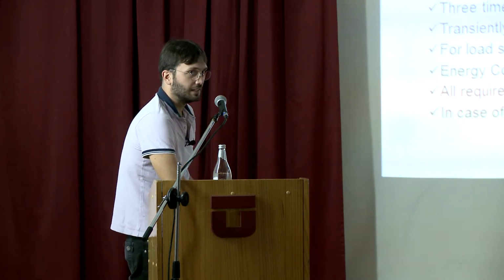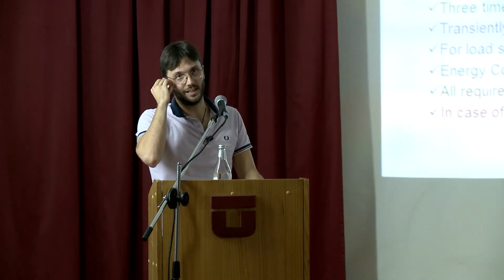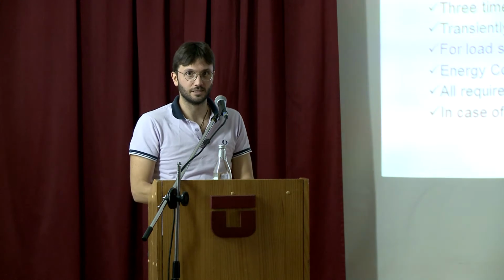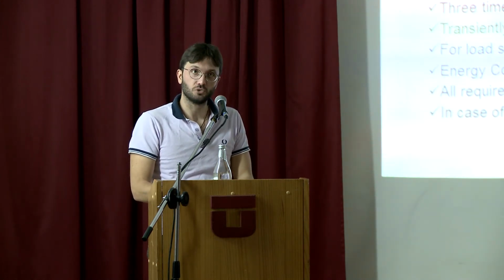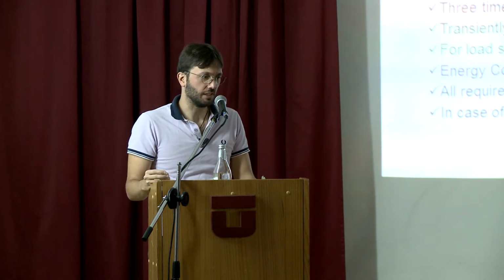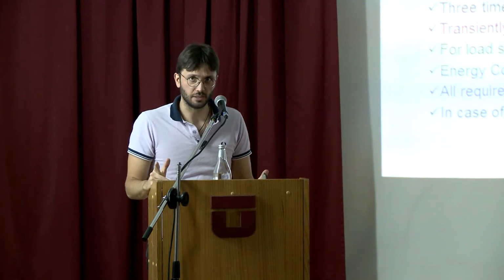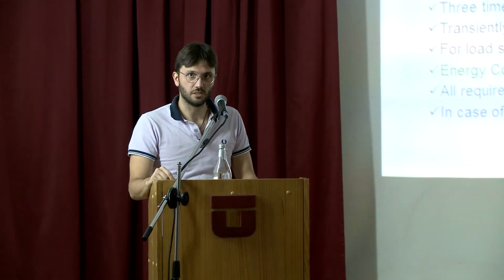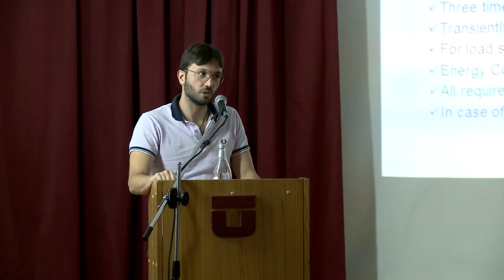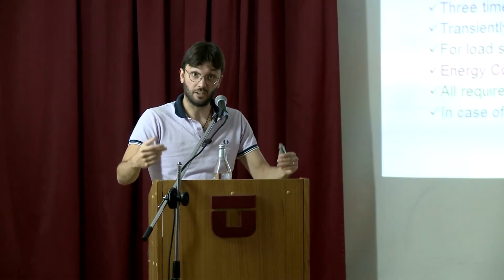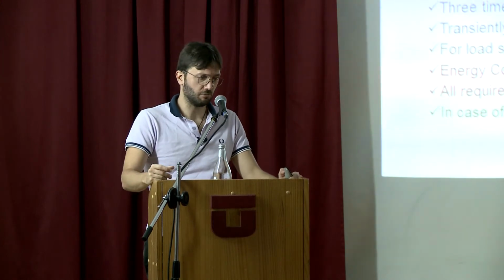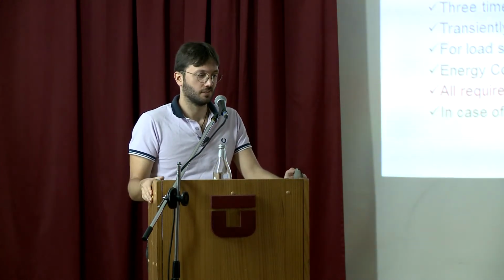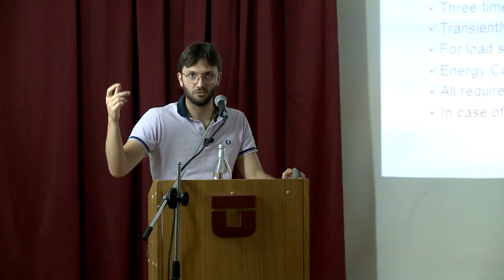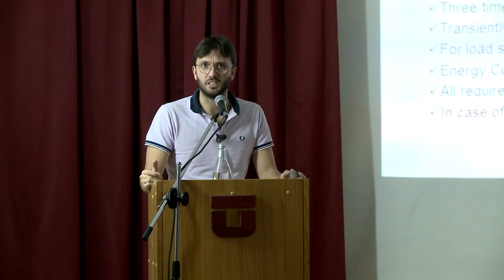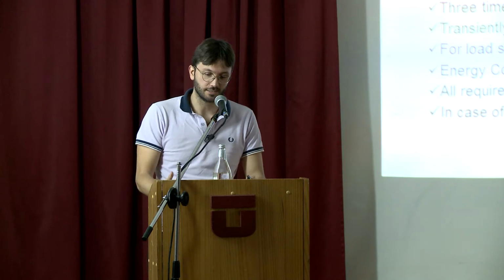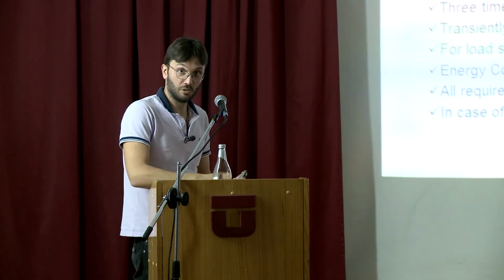This CVR is something that is done already with the tap changer, and is again a simple idea, and I call simple ideas, sometimes it works very well. You are reducing the voltage. I mean, nobody really needs the voltage to be 230. It can be maybe 220. So this variation of the voltage, considering all the constant impedance loads that are connected to the grid, maybe makes me save, I don't know, 5% of coal, 5% of CO2 more. And again, nobody feels it. I don't feel it in the hair dryer that the voltage is 5% lower. But on a global scale, 5% can actually be a lot.